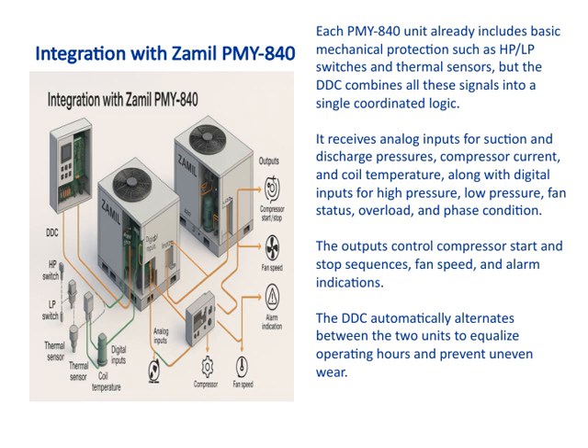The outputs from the DDC then regulate critical functions like starting and stopping the compressor, adjusting fan speeds, and even triggering alarms when needed. An important feature is that the DDC automatically alternates between the two units, which helps to balance their operating hours. This prevents uneven wear and extends the overall lifespan of the equipment. Connecting these points back to our overall theme, this integration highlights how modern control systems not only improve safety and reliability, but also optimize performance and longevity for our HVAC solutions.